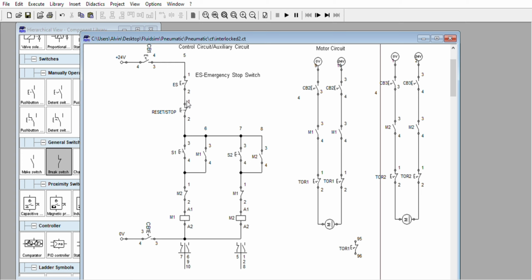Let's say the machine requires some station wherein the operator can operate the stop around the machine, so you can add the normal reset stop button, or however many emergency stop push buttons you can add, as many as you can, as long as it is safe to emergency stop the circuit. Always in series, breaking the circuit, that is a normally closed contact. Turn again. Okay, stop. Okay, so M2 is preventing M1 from functioning because once this one is turned on, that is open, opposite to the normally open contact.